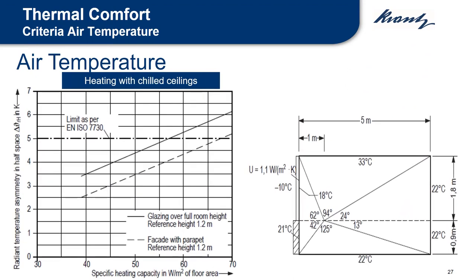One should note that the radiant temperature asymmetry is calculated using the surface temperatures of the enclosing walls, ceiling and floor and their angles of radiation. The latter depend on the location of the workplace. As a rule, it has to be checked whether the workplace nearest the facade complies with the criteria. The heating capacity of a chilled ceiling is restricted in order to satisfy the limit of the radiant temperature asymmetry.